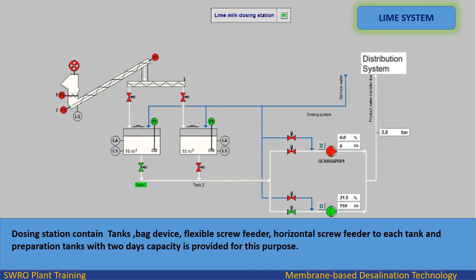The lime milk is prepared in the lime dosing station, which consists mainly of the following equipment: a bag device with mixer, an exhaust fan, a flexible screw feeder with level switch, a horizontal screw feeder to divert lime powder to the tank, two dosing pumps with 100% capacity each. It is required to flush regularly the dosing lines upstream and downstream of the pumps.